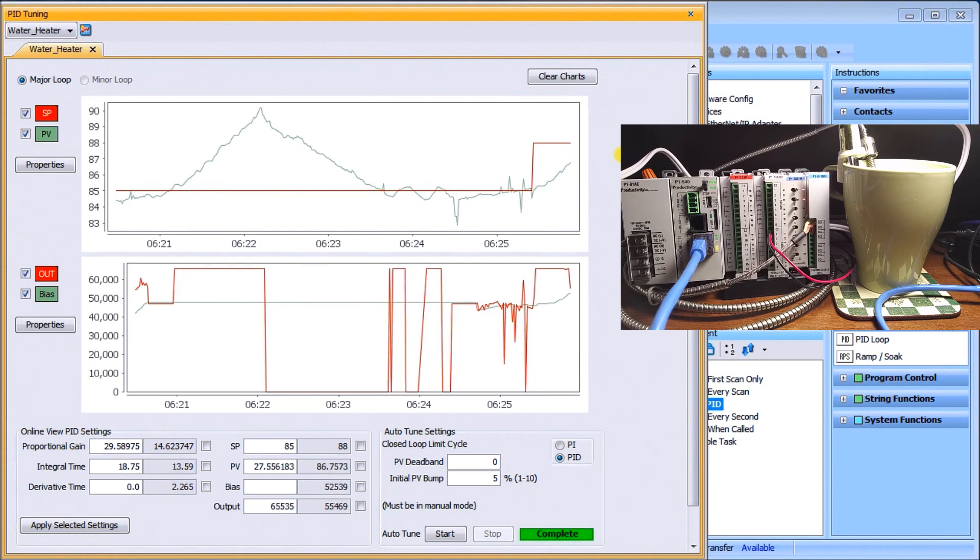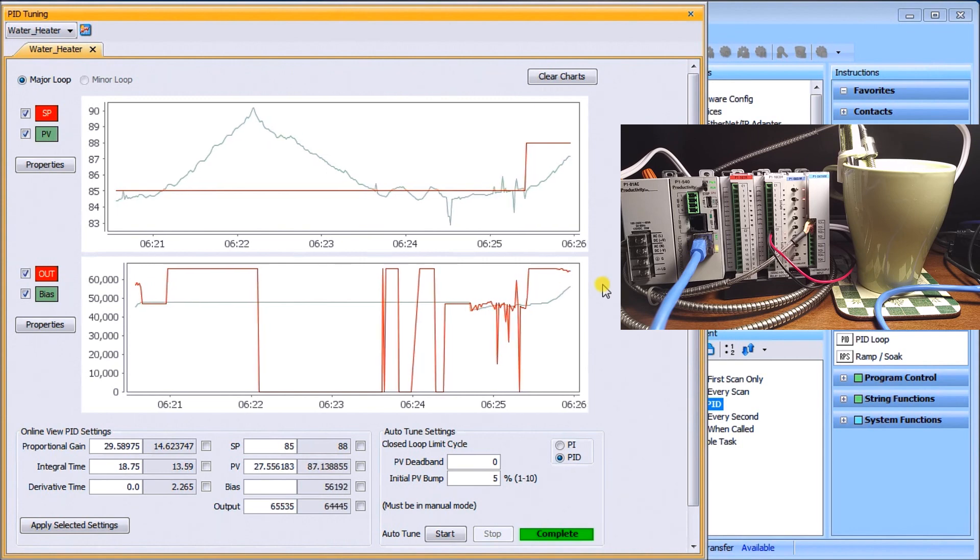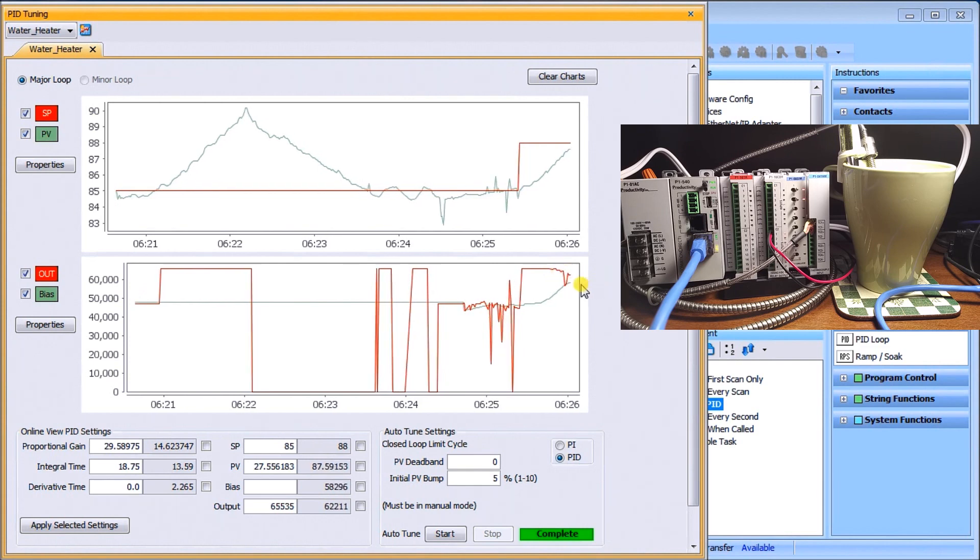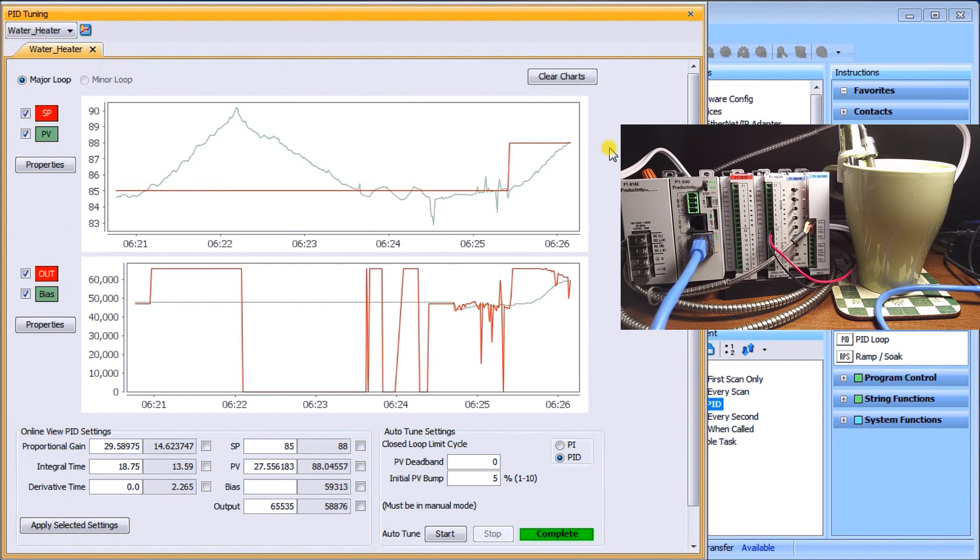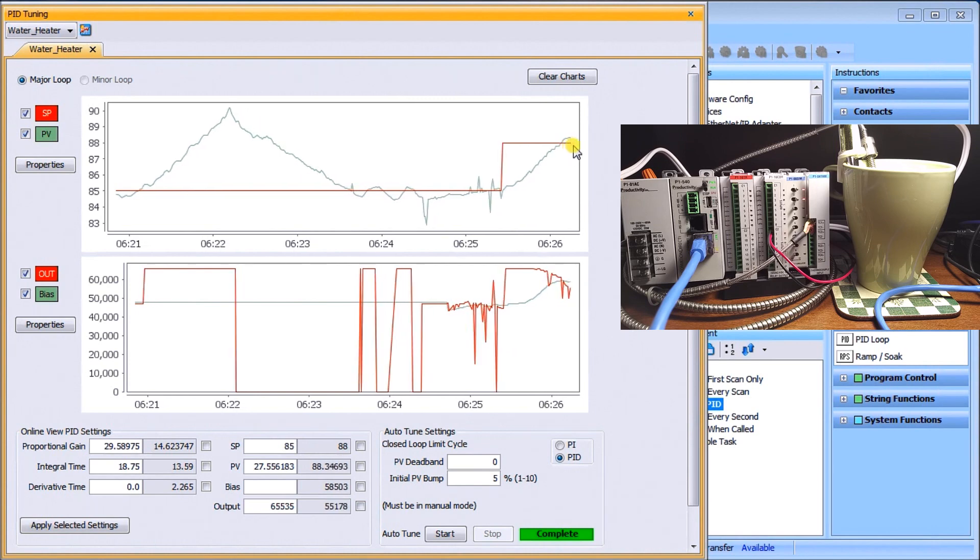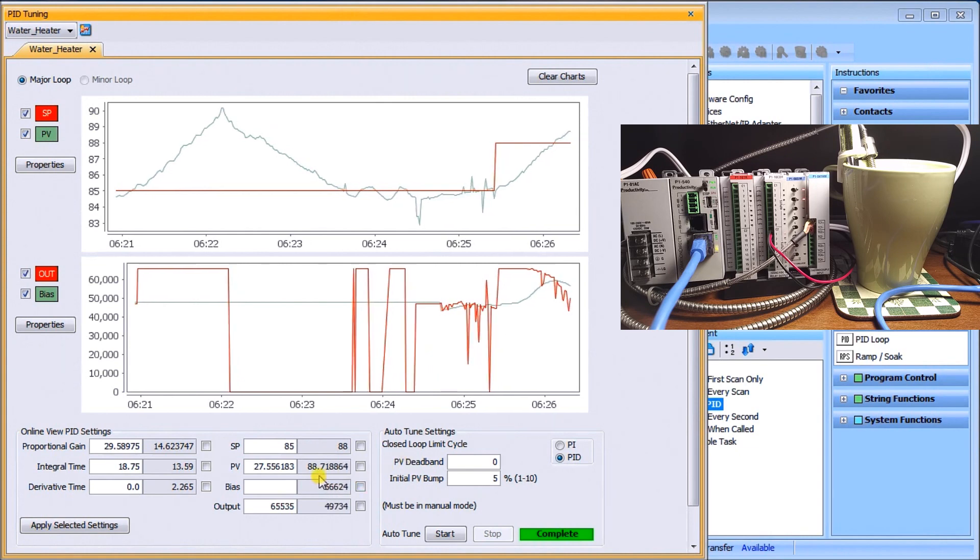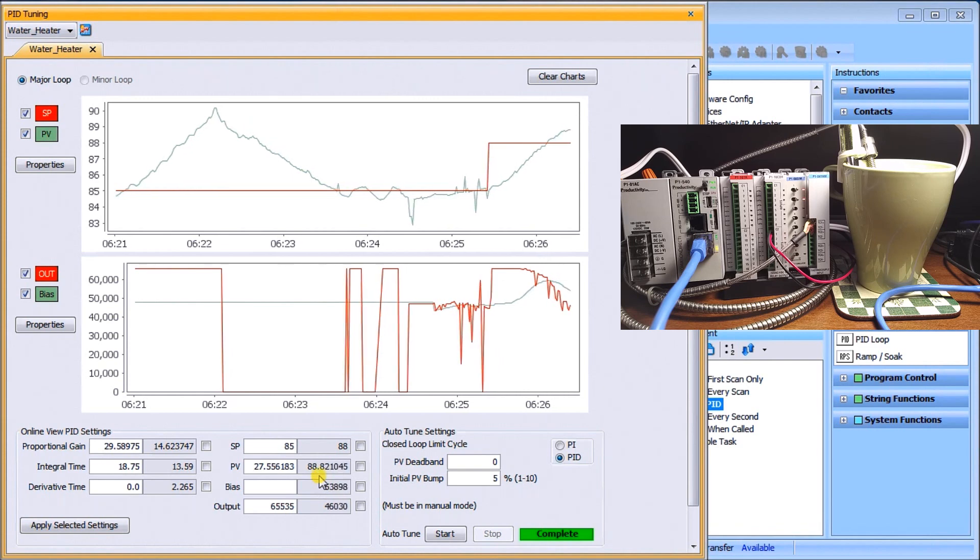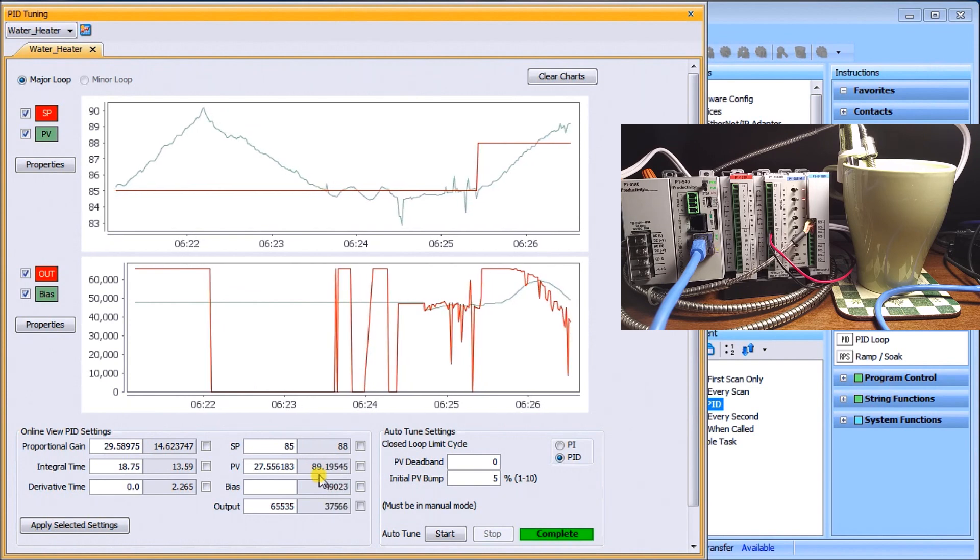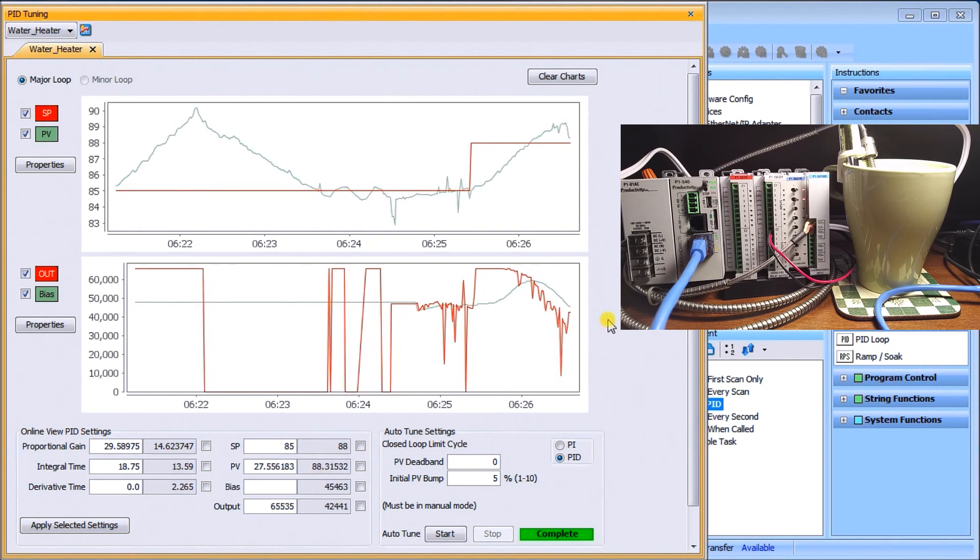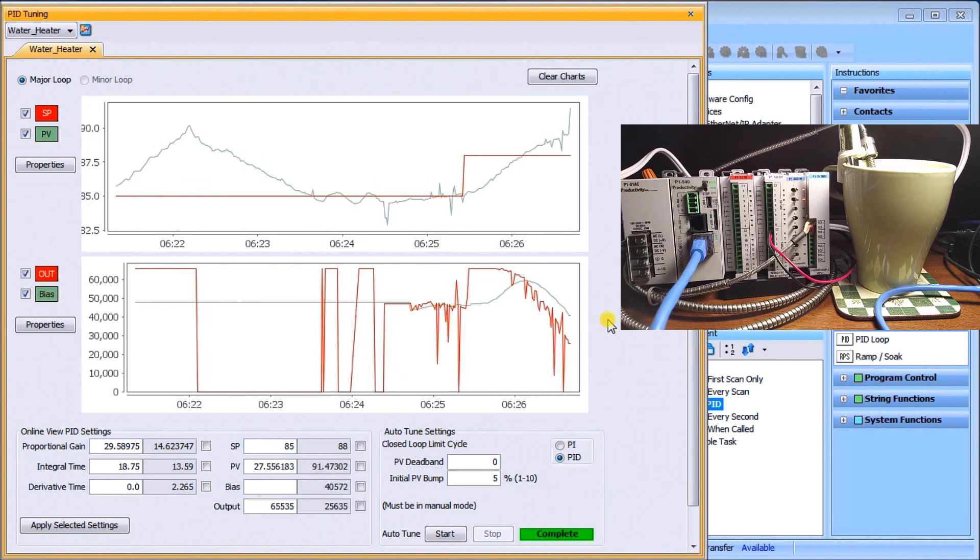You can see how my output is actually oscillating a little bit to try to maintain that temperature and with minimal overshoot. So we've actually hit our target. We're actually about 88.7 right now. So it looks like we've kept within about one degree tolerance for that initial overshoot, and then what you'll see is now it'll settle back down and we'll get right to our target.